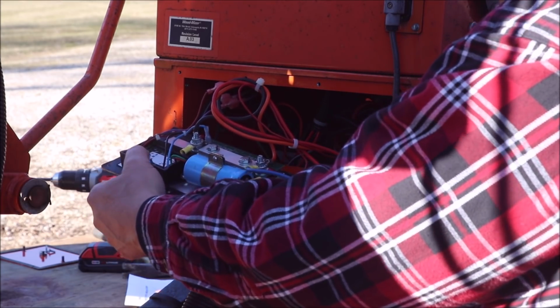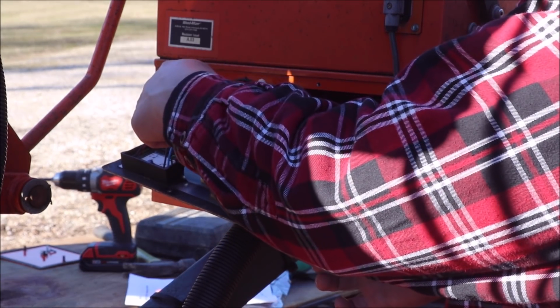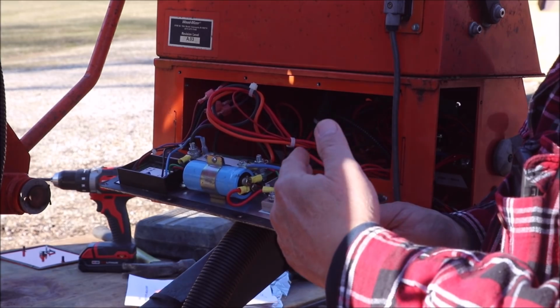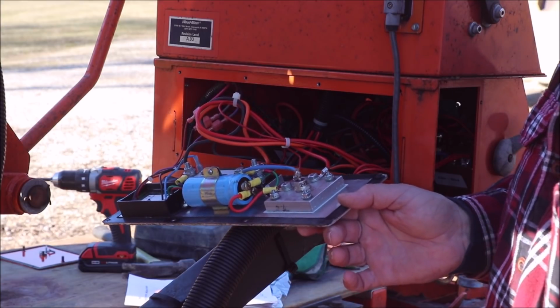This is the control board that's faulty. This is the heat sink down here. It's got a diode on it. And then this is the MOSFET board. And that's what controls the power feed for forward. So what we want to do is get this guy removed from the board, get the new one in place, and then I'll bring you back once I've done all that.